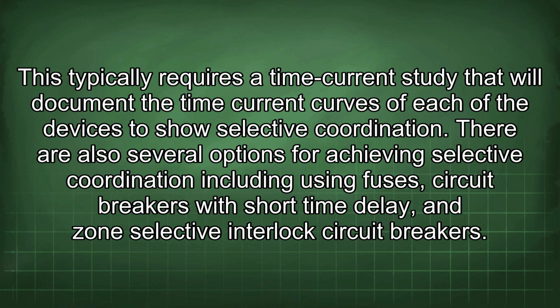This typically requires a time current study that will document the time current curves of each of the devices to ensure selective coordination. There are also several options for achieving selective coordination, including using fuses, circuit breakers with short time delay, and zone-selective interlock circuit breakers.